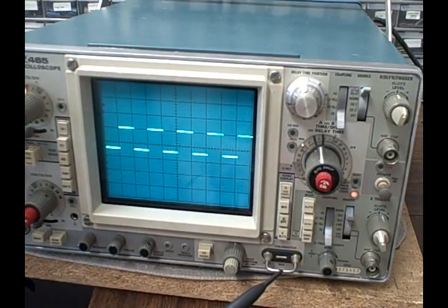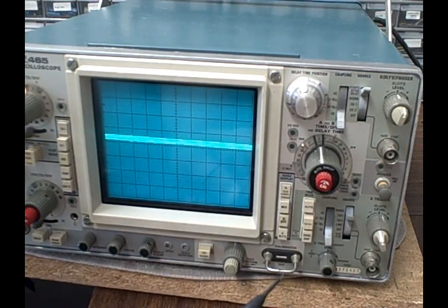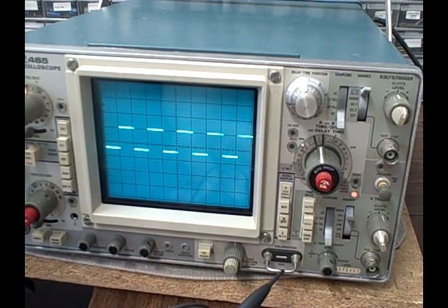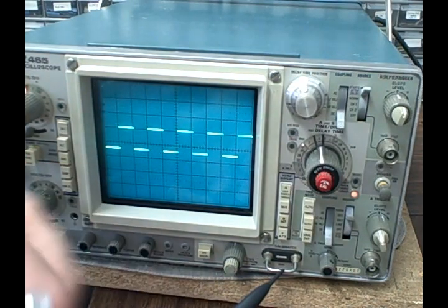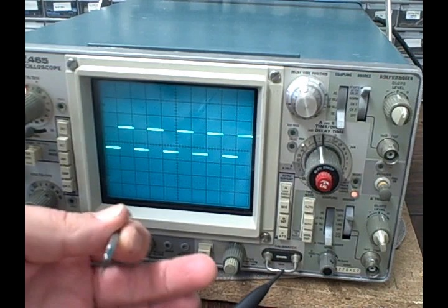Okay, so now we're going to take a look at the calibration test point, and to do that we're going to use our probe. And when you're trying to adjust the capacitance of the probe, you want to be in the times 10 position. This is the high impedance position, and it, in conjunction with the capacitance of the probe, makes the adjustment a lot more significant. Let me give you an example here. Right now we're actually properly adjusted, but we're going to misadjust ourselves here on purpose.